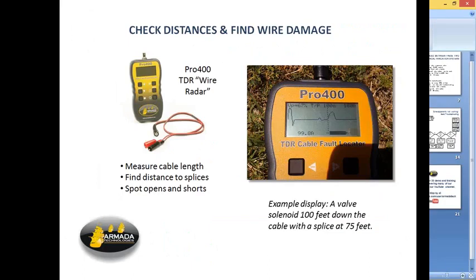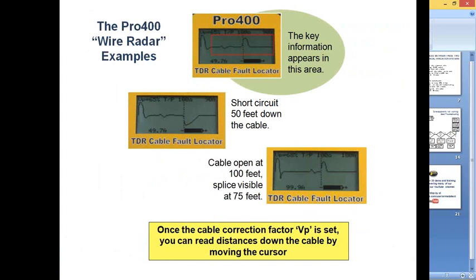So I slide my little cursor line out there, and I read the distance, and it says, oh, 100 feet out, I've got an open circuit. And if I slide my little cursor back to where the little wiggle is, I can see at 75 feet, it says, oh, it looks like there's a splice. Pretty handy thing for being able to locate valve boxes you can't find otherwise. With a TDR, you can see a perfectly good splice and see the distance to it. The trick is in calibrating the correction factor for the cable on this device so that the distances read right.